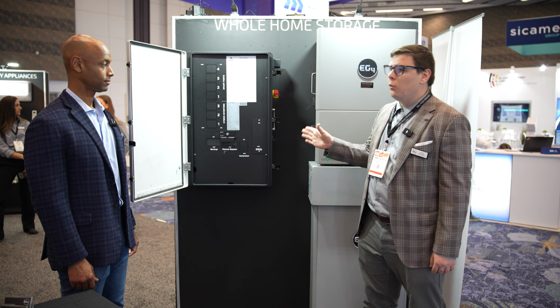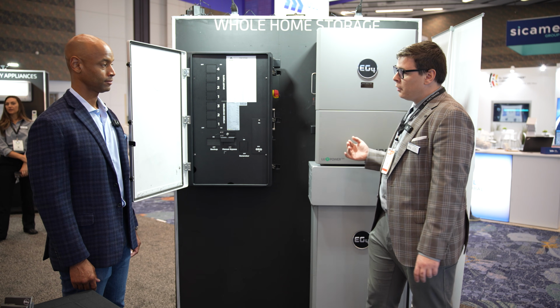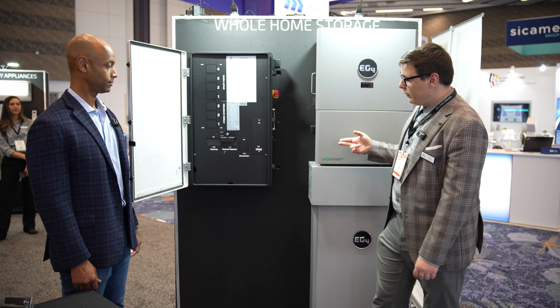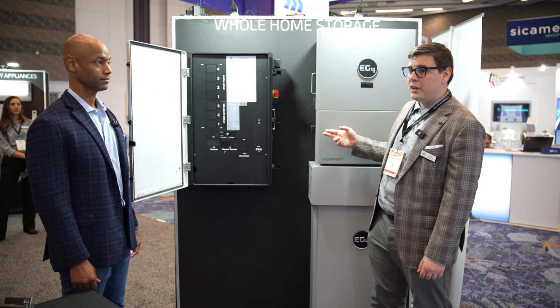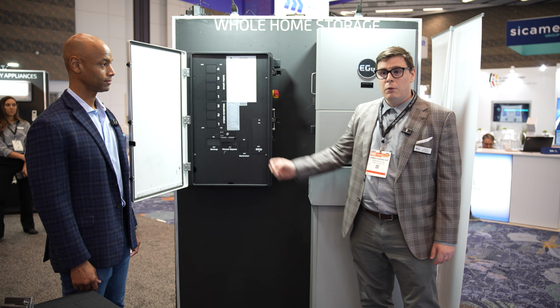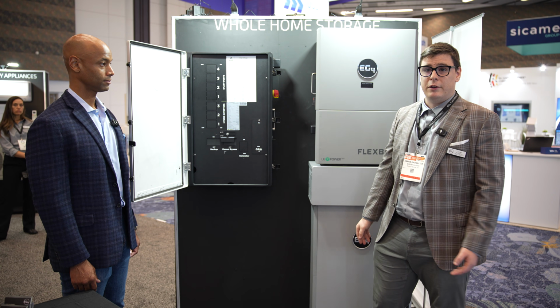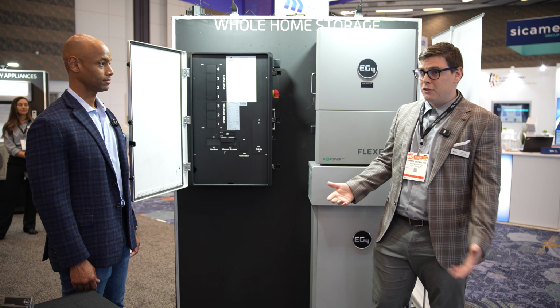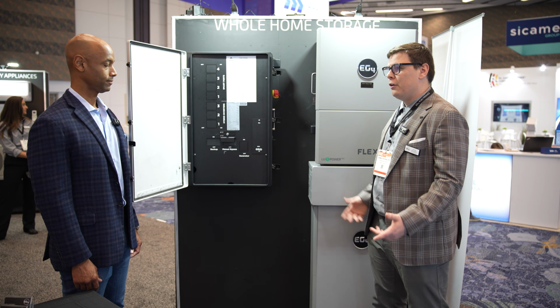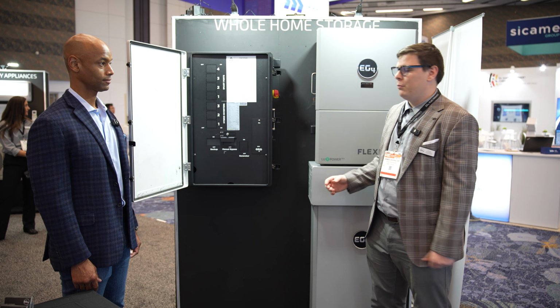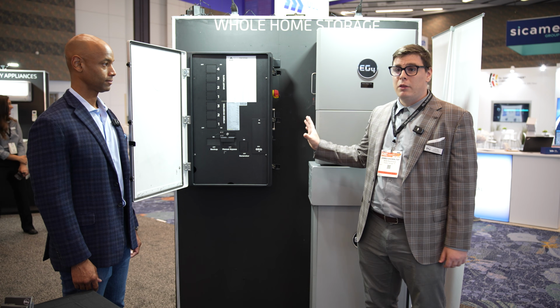If your grid company still wants an AC disconnect on the inverter, remember, you're only running 60 to 70 amps from the inverter to the gateway. That means you can buy a 100 amp knife switch. Those are exponentially cheaper than 200 amps - about $100-$150, depending on where you buy them. So we saved you a lot on that.